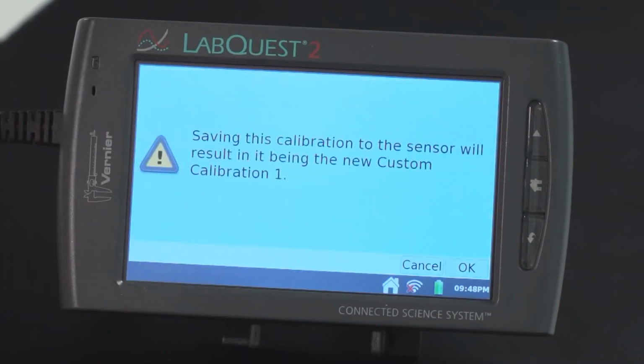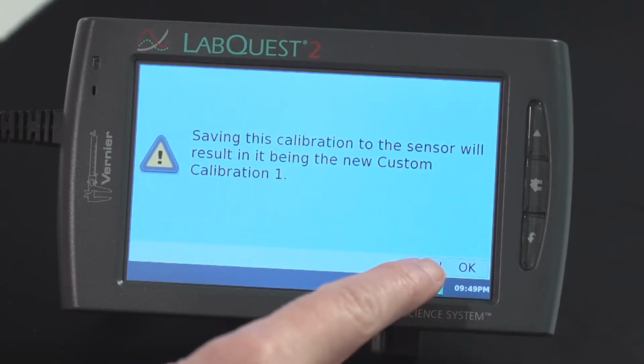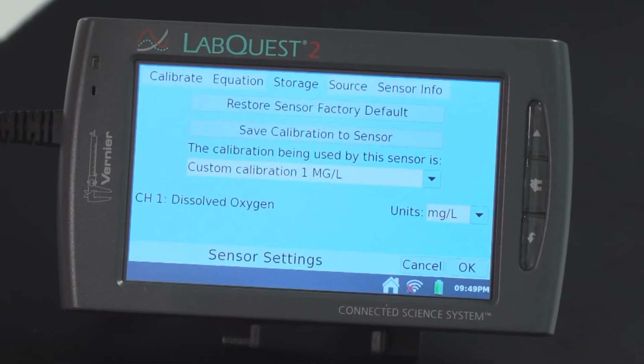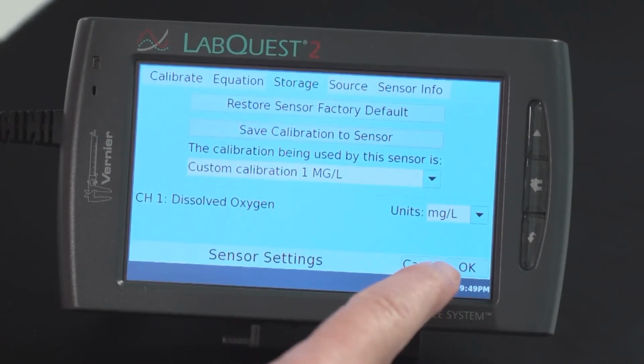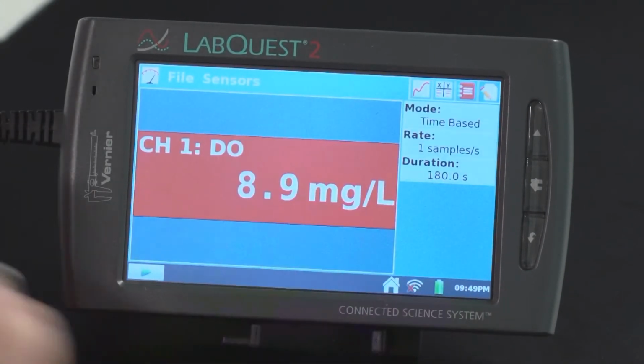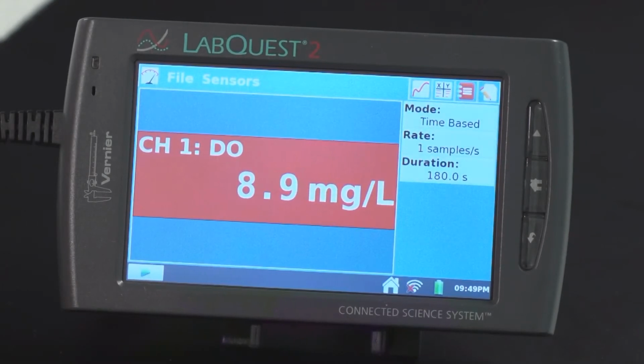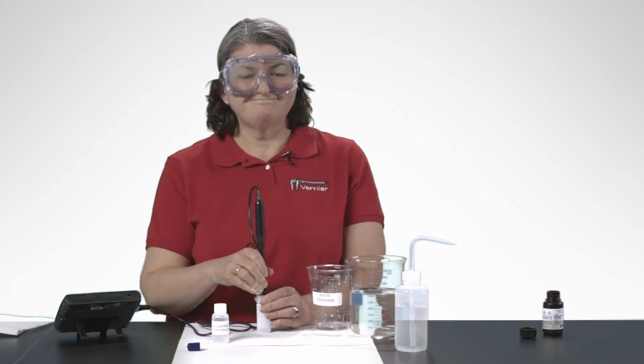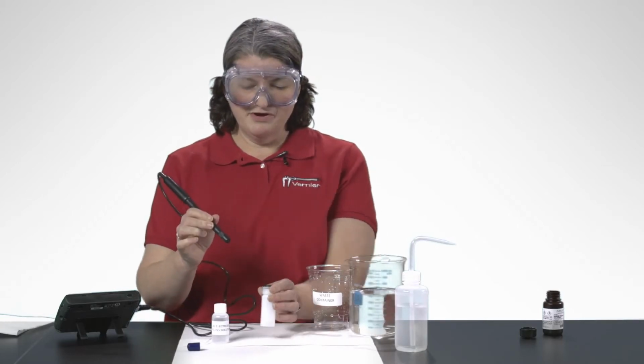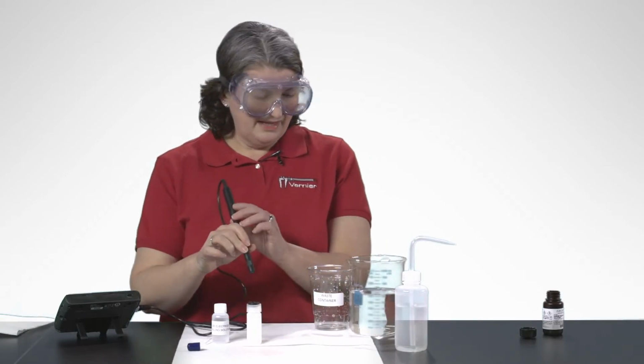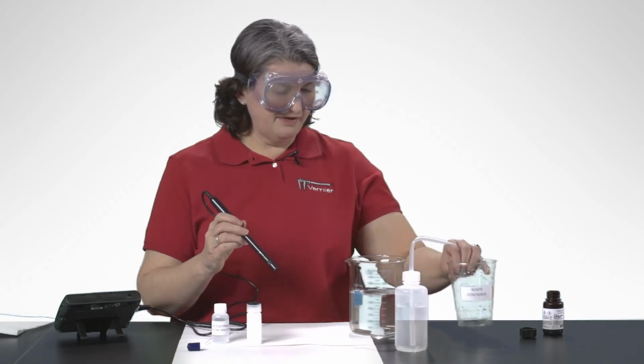So I'm going to tap that. It says I'm going to save the calibration. Good, that's what I want. So tap OK. And that's done. We can say OK again to get back to the main screen. So the calibration is done and the calibration is saved. I take it out of the bottle, and now I'm ready to actually take my measurement.